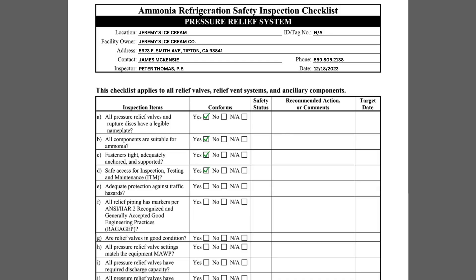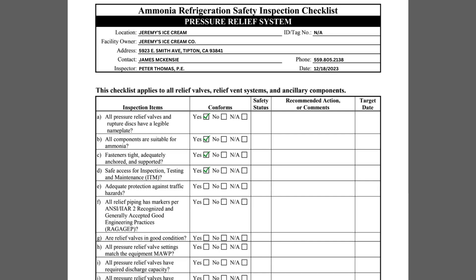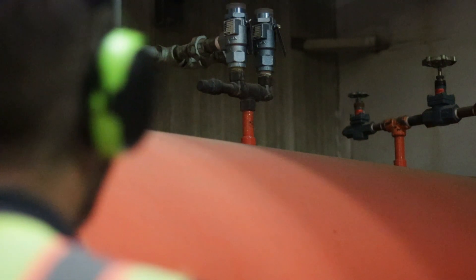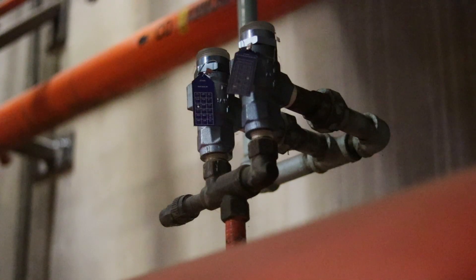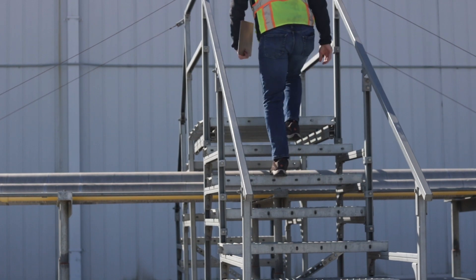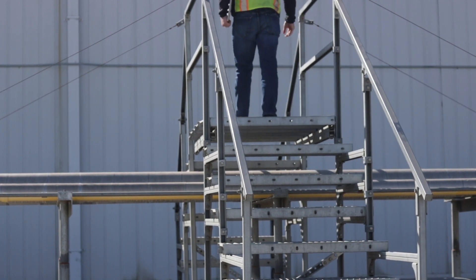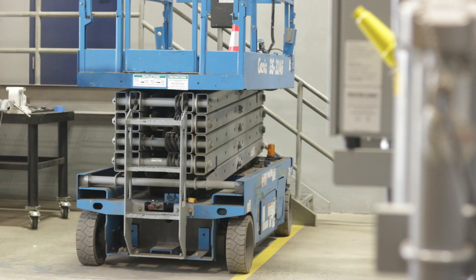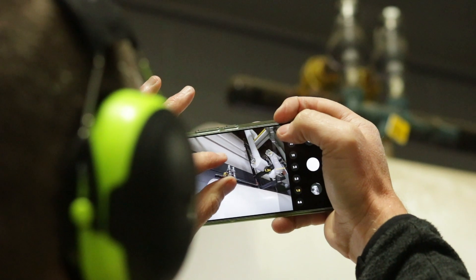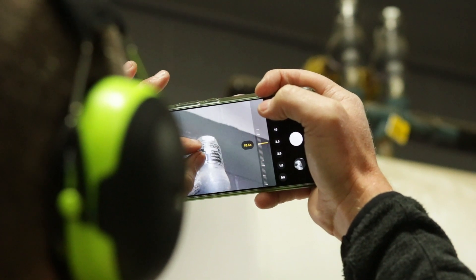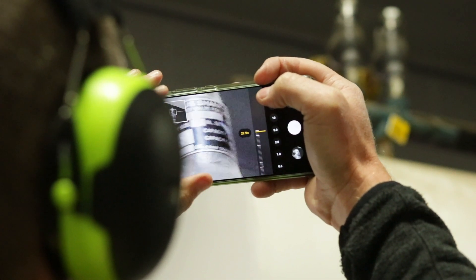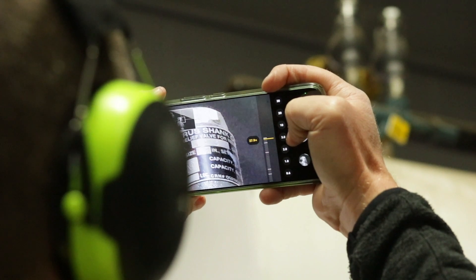The pressure relief valves should have safe access for normal service and maintenance. Ideally, permanent ladders, catwalks, or other means to access the system's relief valves will be available. When permanent access is not provided, facilities must utilize extension ladders or aerial lifts to access high or hard to reach places. For difficult to access relief valves, a camera with a high quality zoom lens can save a lot of time associated with moving ladders around.